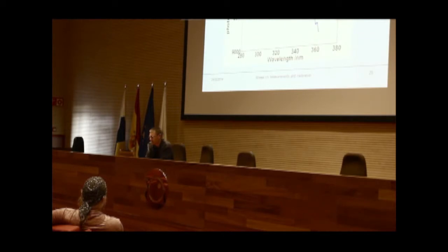So this is just an example of how a responsivity will look if you measure a lamp with your Brewer. This is an example of a double Brewer, 163, that's mine. You will see here about 10,000 photons per second for 1 milliwatt per square meter and nanometer of radiation.